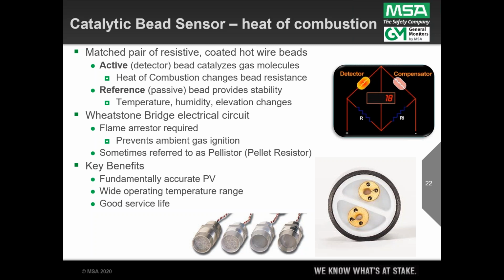And so you've got to have a flame arrestor. That's what prevents these hot wire beads from actually igniting the gas, should there be flammable gas there. They're sometimes referred to as a pellistor, which is a compilation of the words pellet resistor. So in England, they call it a pellistor. But what's really neat about this technology is it's fundamentally accurate without any microprocessor. You don't need anything to process the signal. It's a millivolt signal coming out of that circuit, and that's shown in the upper right-hand corner.